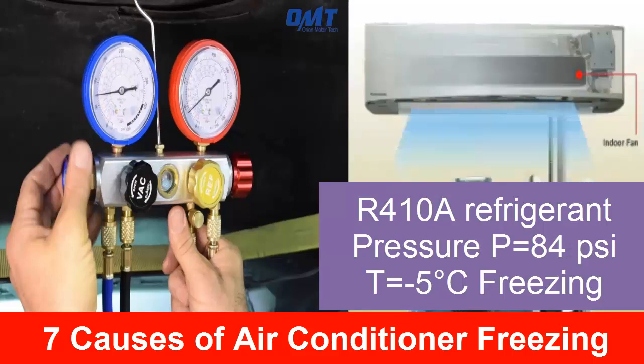When the refrigerant leak is larger, the freezing may disappear, due to the fact that the unit presents a totally unbalanced cycle. Remember that oil stains indicate a refrigerant leak. Remember that low refrigerant charge has a lower than normal current consumption.